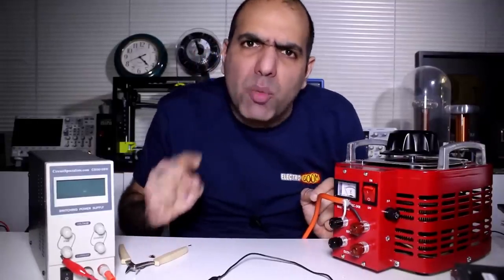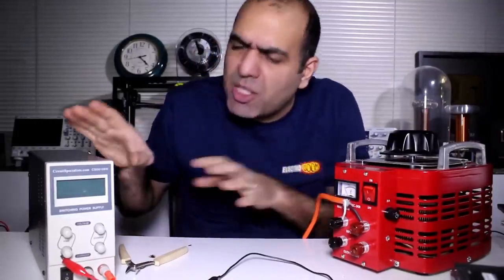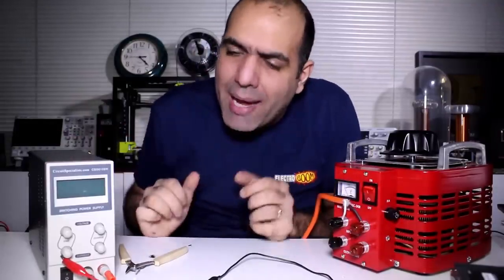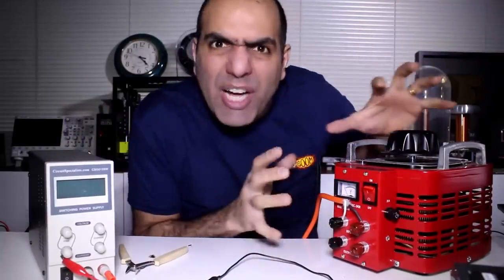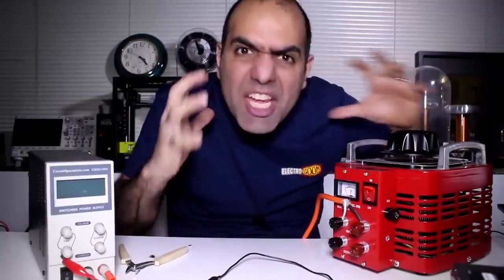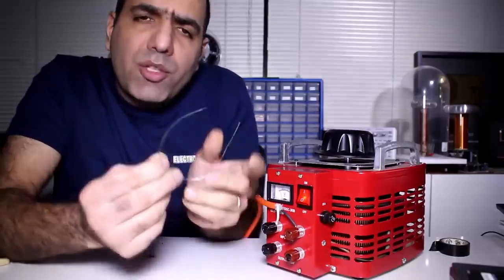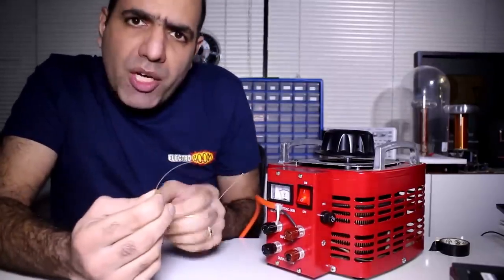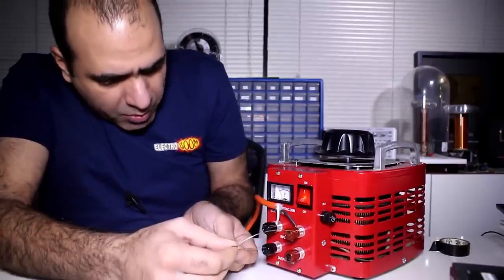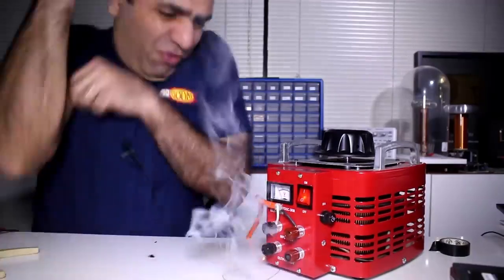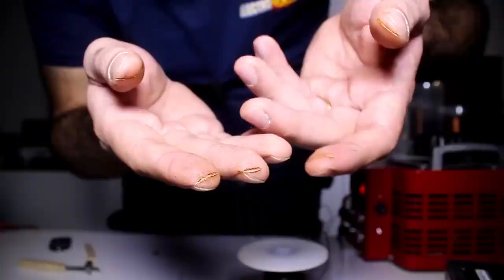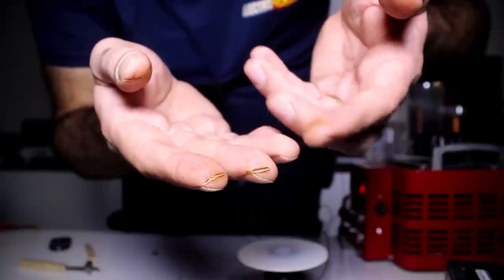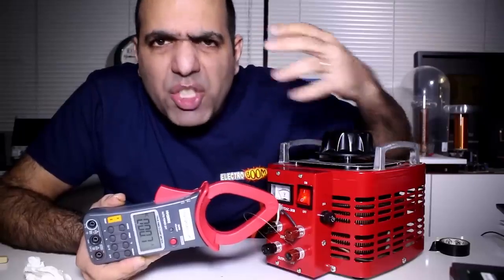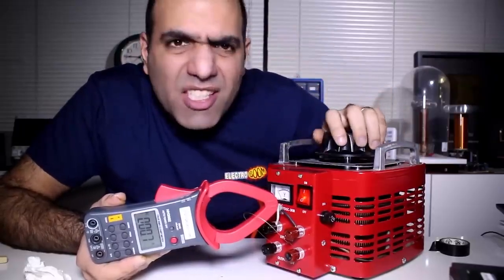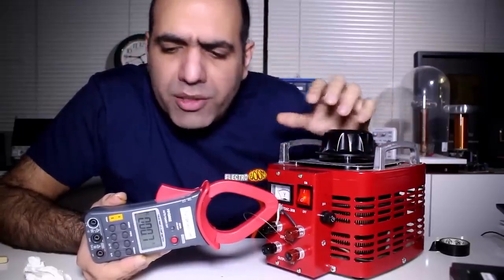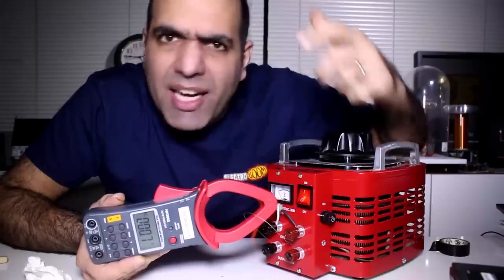I want to be able to measure up to 100 amps, but my supply here can't output more than 10 amps. So I'm going to use my auto transformer that can output some high AC currents. I have a piece of 22 gauge wire here which I'll measure the voltage across. If I connect it to the output of my auto transformer, I should... and burn my fingers again. The piece of wire simply shorts the AC output, so I start at 0 volt and slowly raise the voltage while I'm measuring the current with my clamp meter.